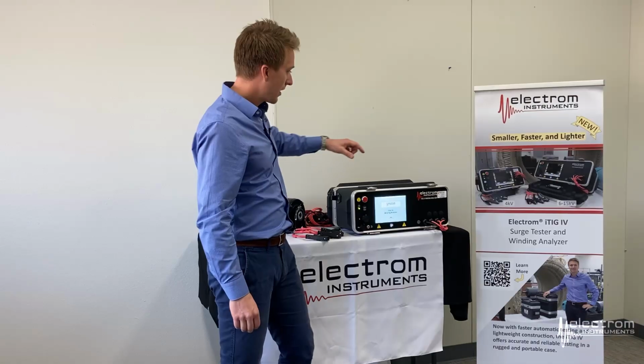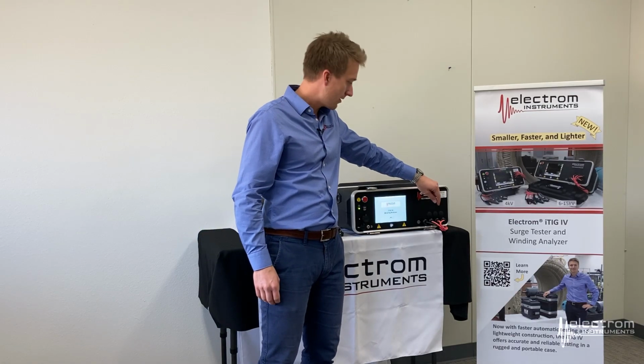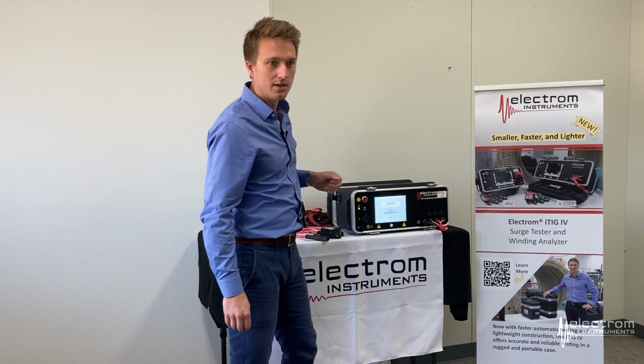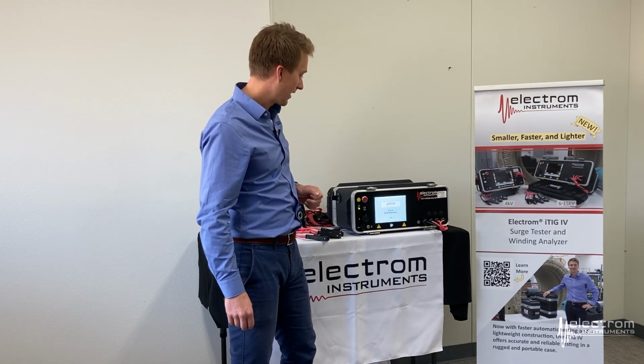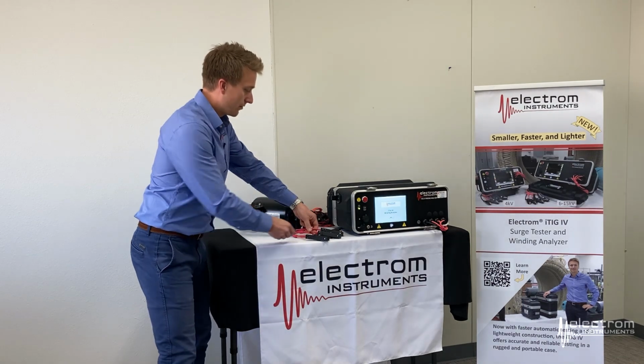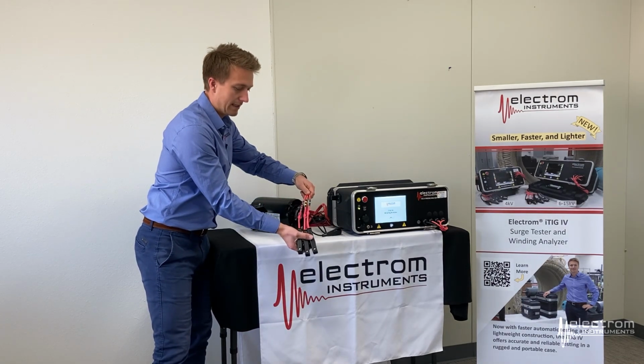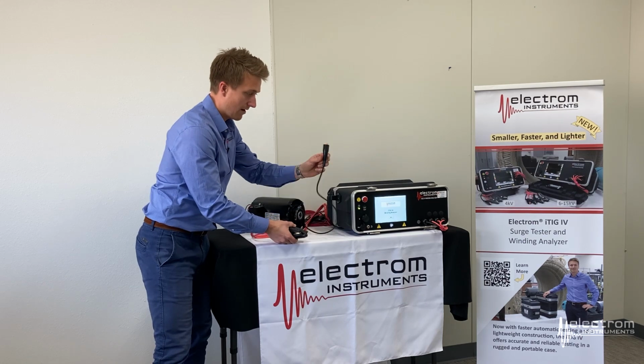All the A models will have 4 high voltage leads, 3 red for phase 1, 2, and 3, plus a black ground lead. Phase 1, 2, and 3 are labeled on the lead set in the clamps, and then you have your ground lead.